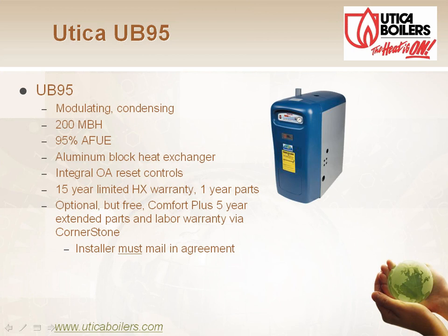There's a free 5-year parts and labor warranty that's available with it. So you just have to turn in a little mailer card, and you can get that free 5-year parts and labor warranty. The really cool thing about this boiler, and one of the reasons we like using it, well, one, it's cost effective. It's less expensive than some other boilers out there. But two, it's really good for direct replacement on an existing system. By that I mean, if you remember I talked about on those stainless steel heat exchanger boilers from HTP and from HTP's competitors, you have to do primary and secondary piping. You got to have one loop for the boiler and a second loop out there in the field taking care of the building or the house.